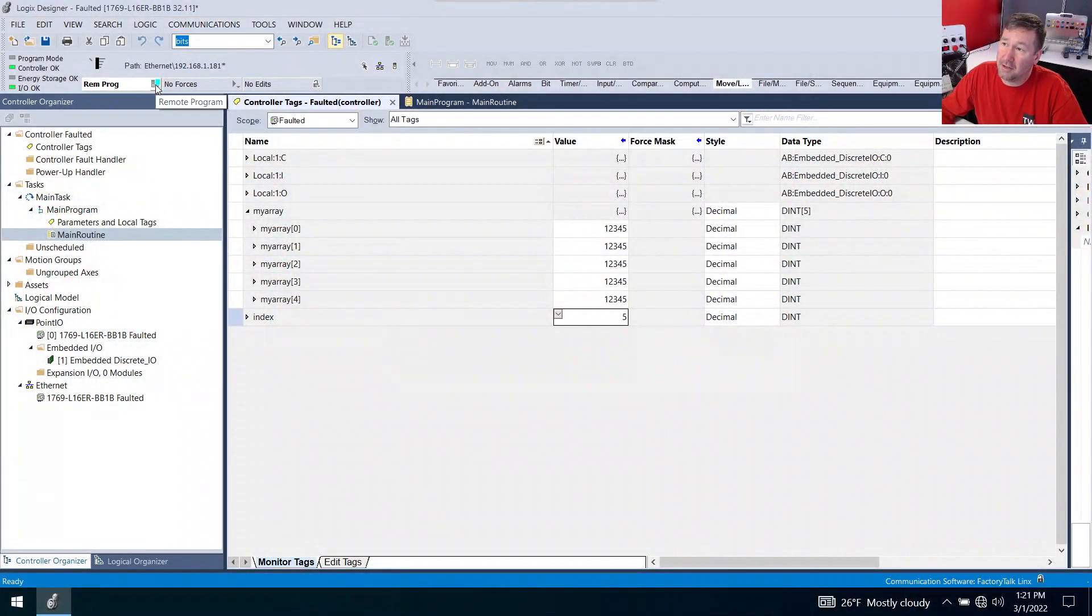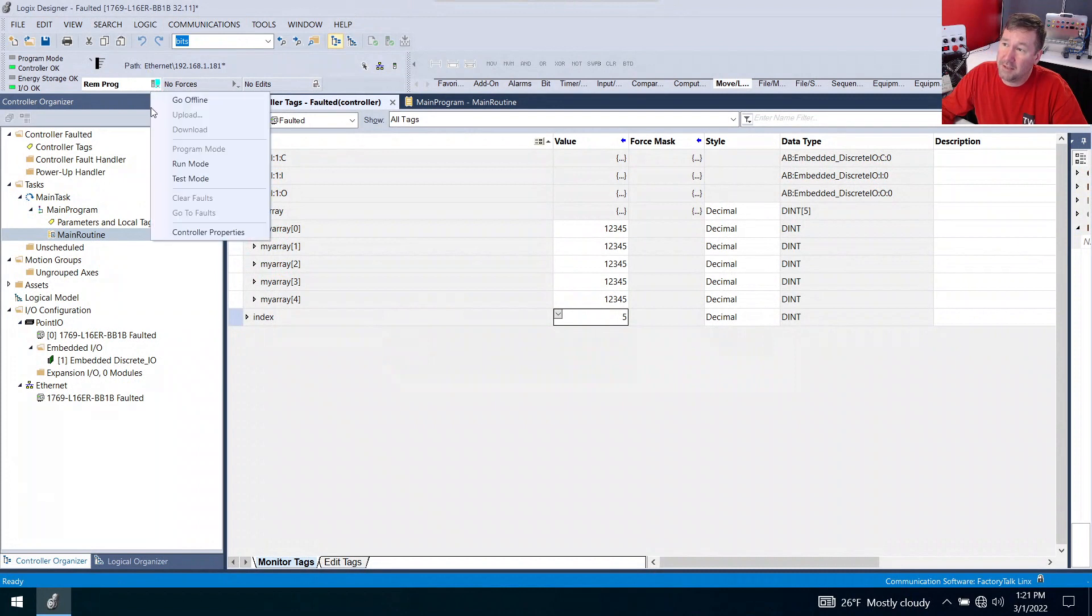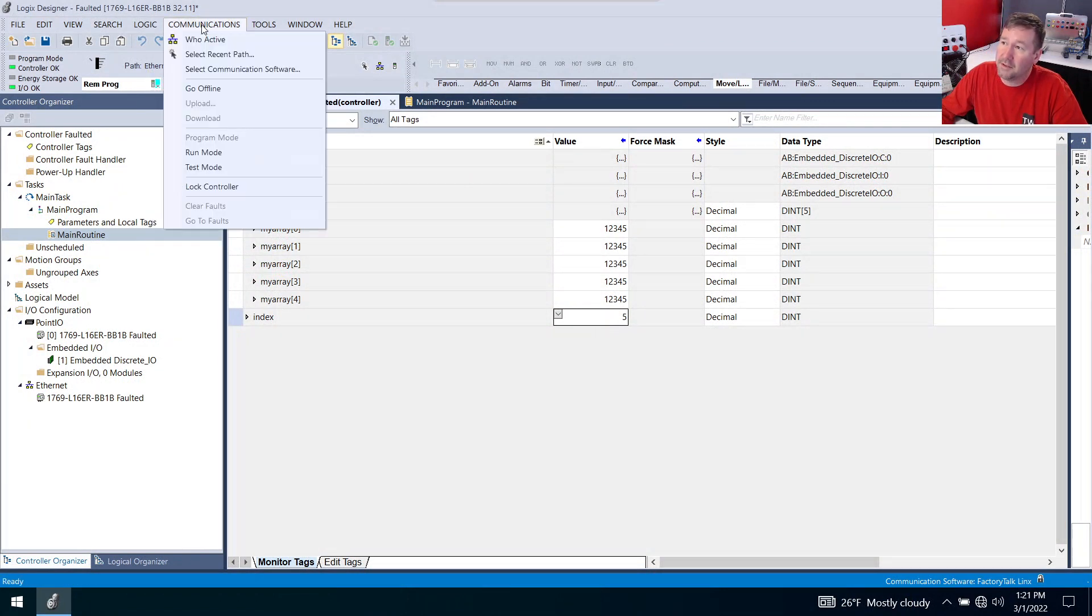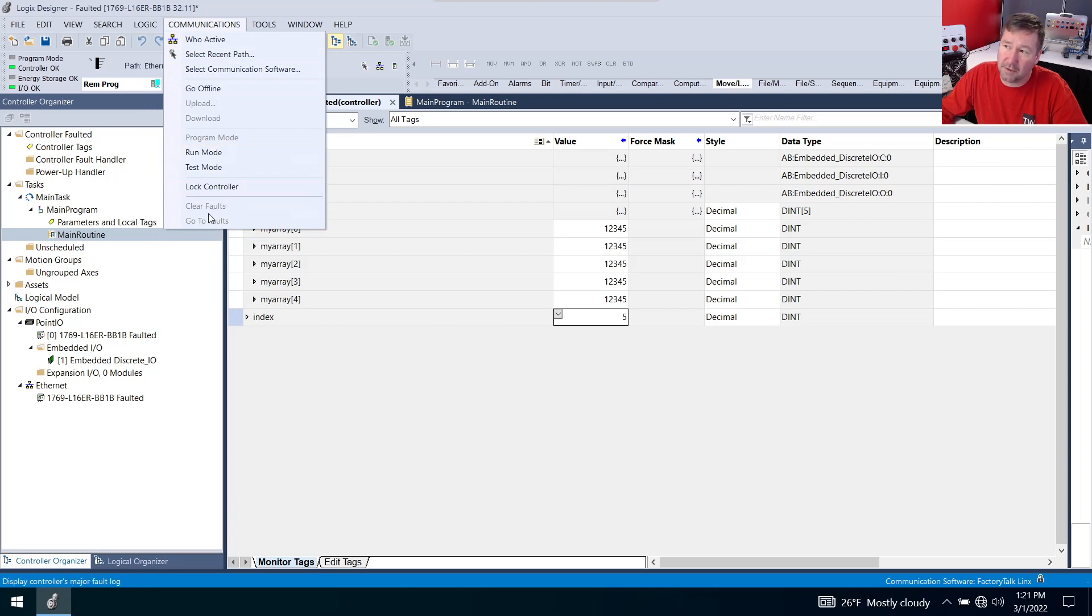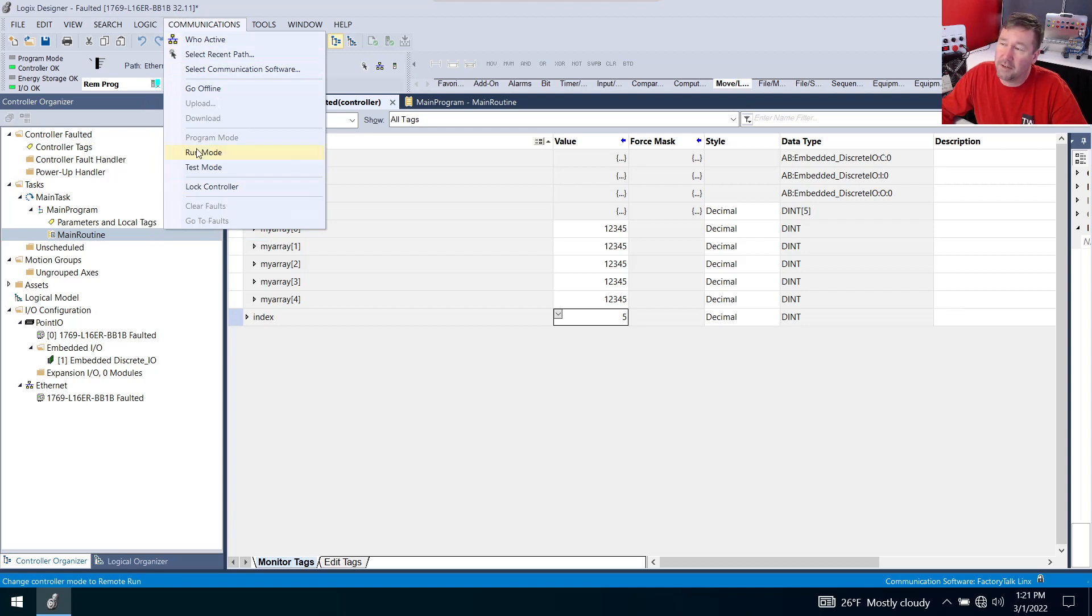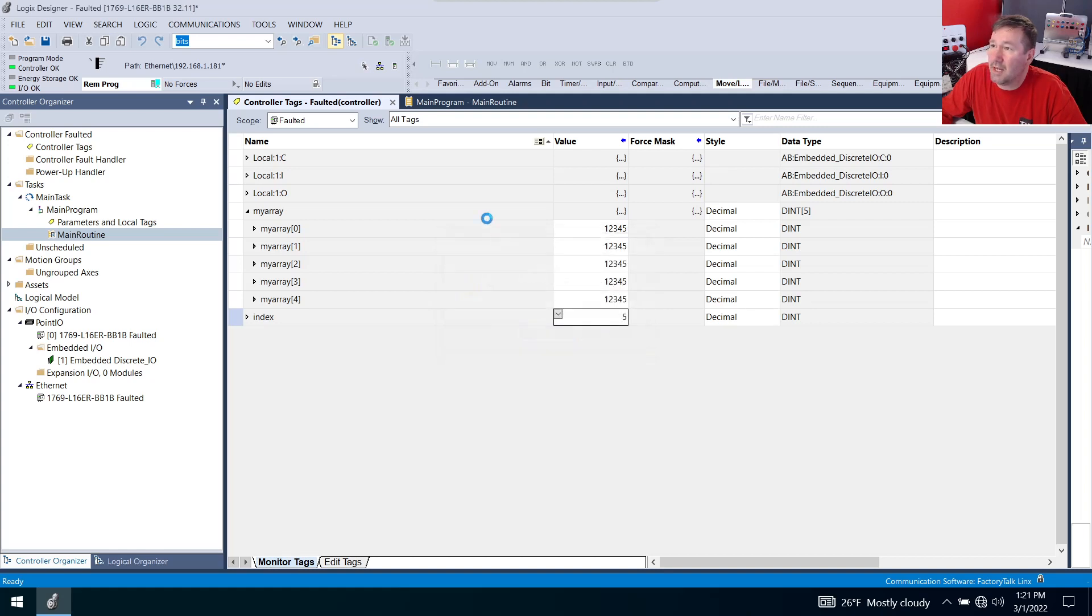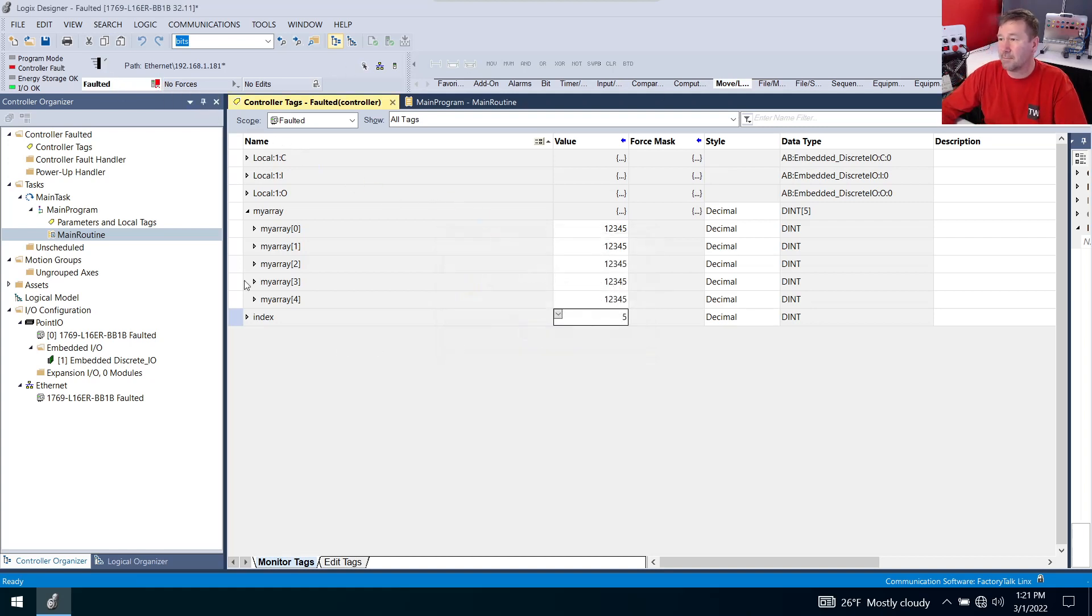And there's several ways we can do that. To the right of the remote run, there's a drop down and we can hit run there. Also under communications, there is a run mode right there. Also the clear fault and go to fault right under communications. And I'm going to put it into run and we're going to see that immediately goes back to fault because we didn't fix the problem.